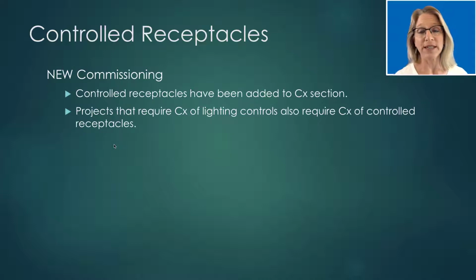So there are a couple of new requirements in the 2018 WSEC for controlled receptacles. They are now included in the scope of commissioning. So our interpretation of the new language is that if commissioning is required for the lighting controls in a space, which is triggered by the total lighting power in the building, and that threshold is 20 kW of lighting power, or 10 kW of lighting power that is controlled by automatic lighting controls, that trigger then also triggers that controlled receptacles are also required to be commissioned. So commissioning, as far as we can tell with the new language, is connected to whether lighting controls are required to be commissioned.